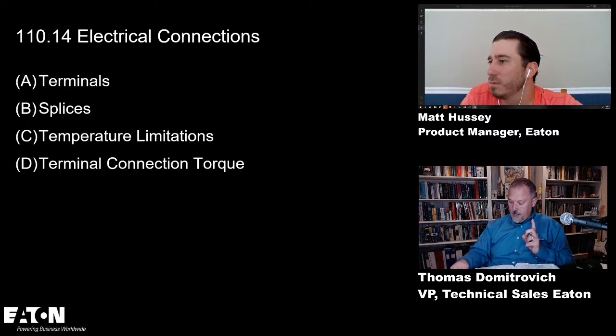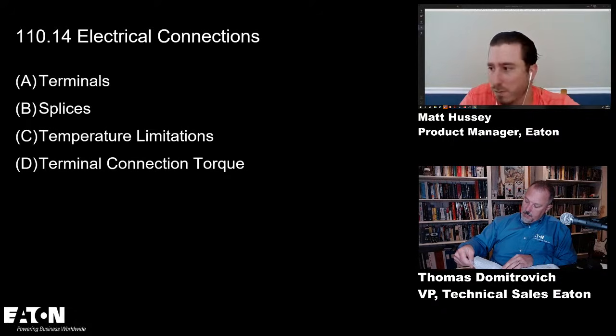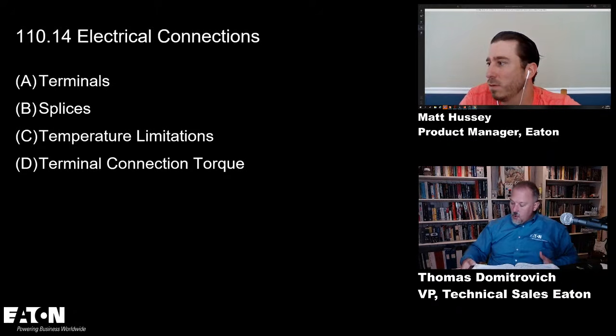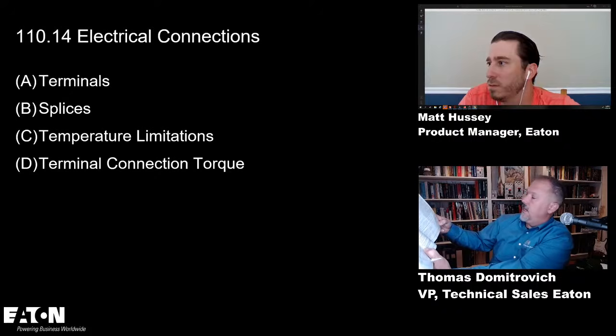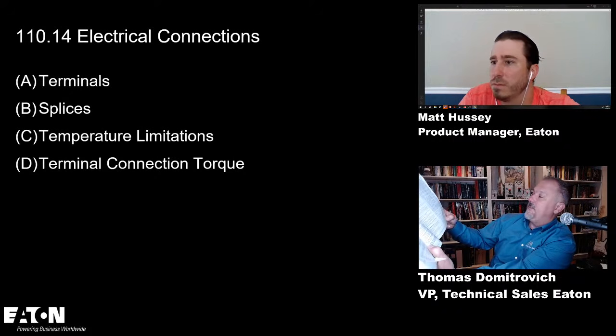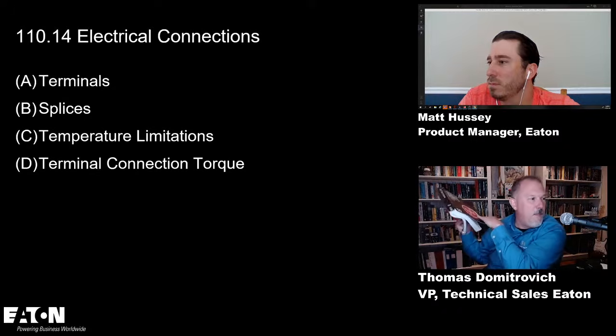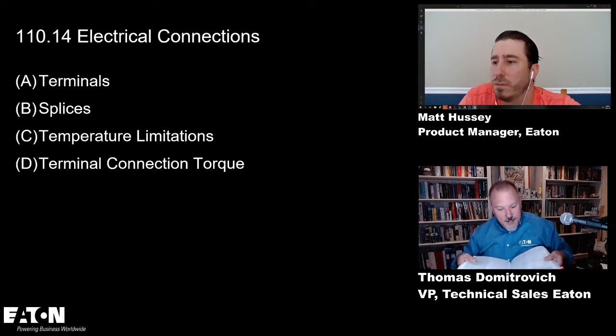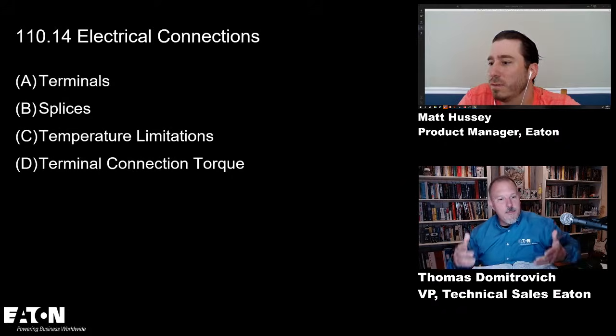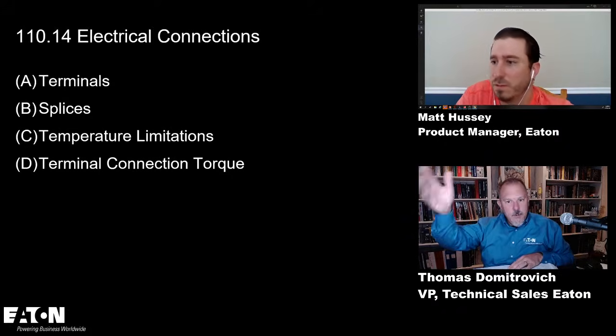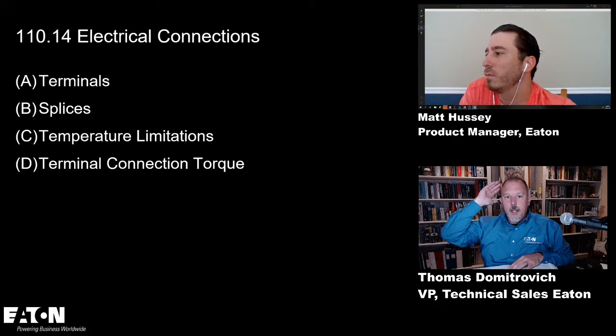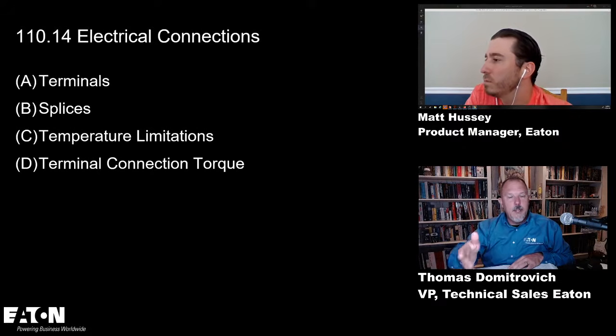3A through 3C. And A3 says, A is features and location, and 3 says not to be located within the same enclosure, panel board, switchboard, switchgear, or motor control center with or without common bus that supplies loads other than the fire pump. Well, there you go. So if you have an MCC, Matt, that's supplying motors that are not the fire pump, then you cannot put that in that motor control center.